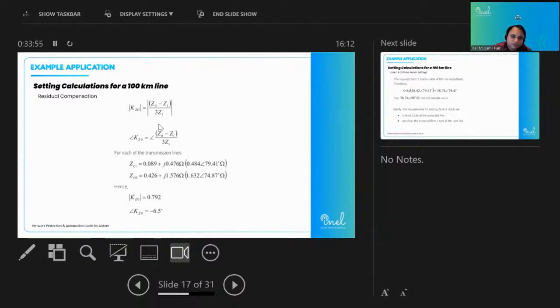So these factors are considered when there is any unsymmetrical fault, single line to ground or two line to ground fault. Its calculation is zero sequence impedance minus positive sequence impedance, divided by 3 multiplied by positive sequence impedance. And we take the absolute value, and this will be the magnitude of that compensation factor. And by this value, we can calculate the angle of that compensation factor.